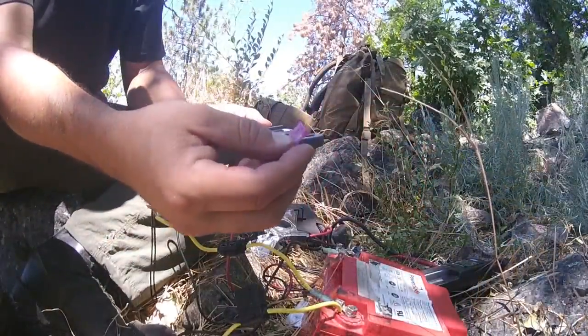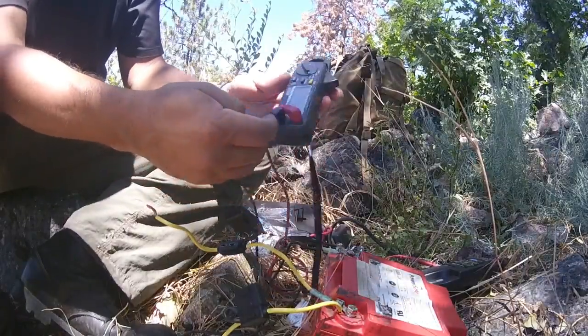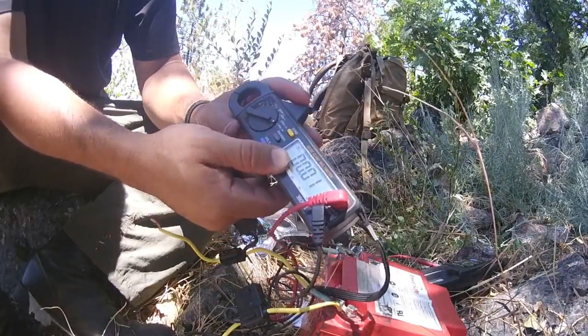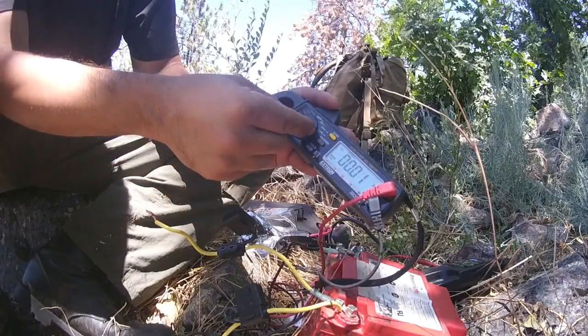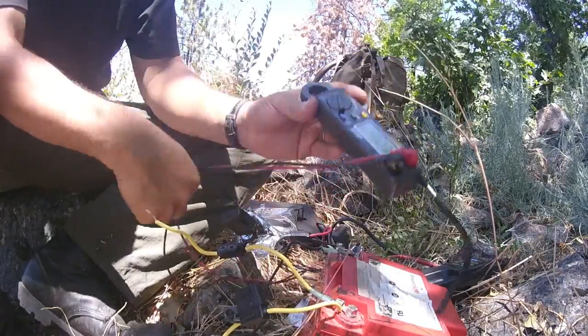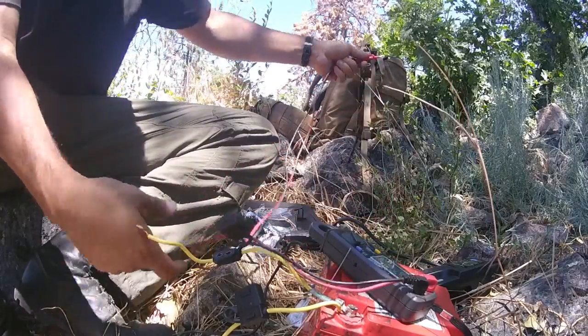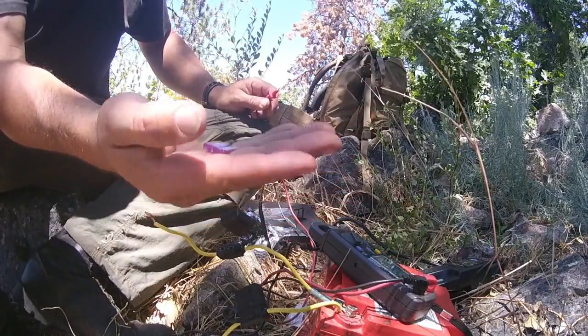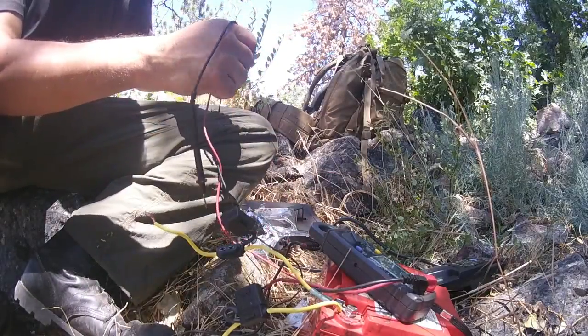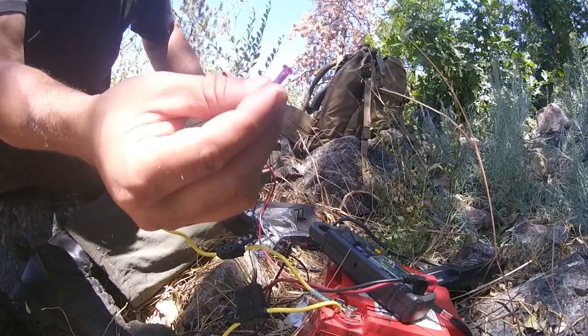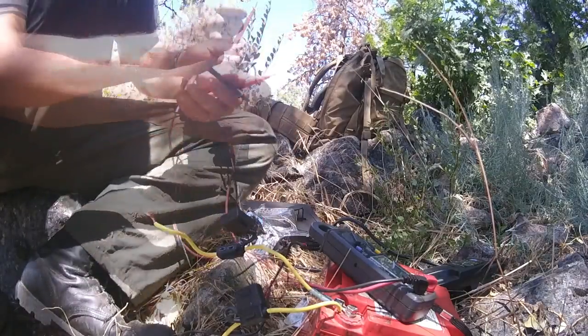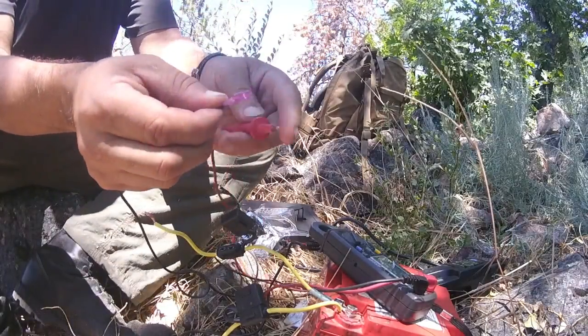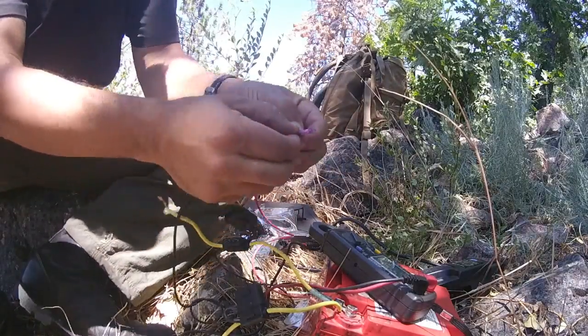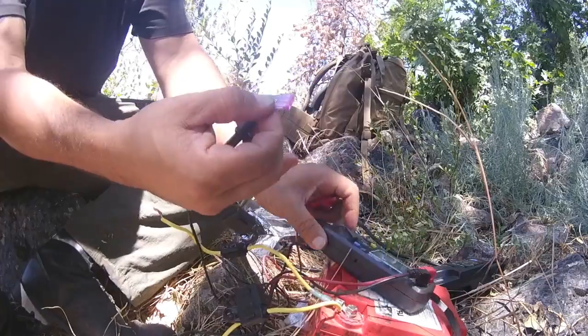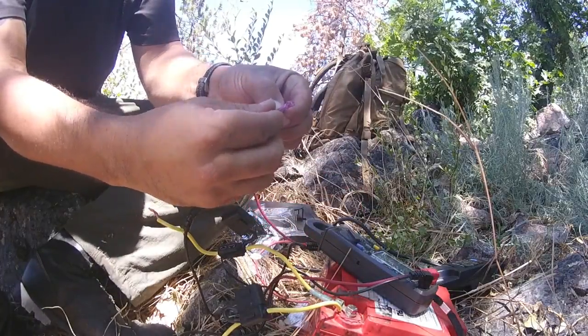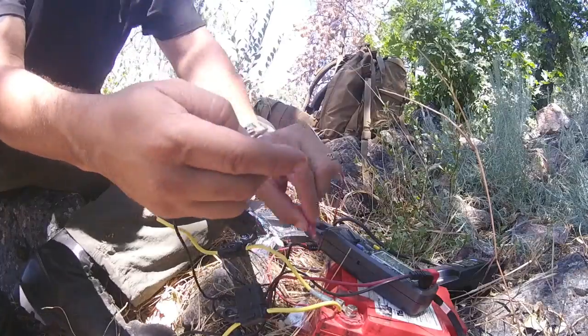So we took the offending fuse off, the suspected fuse. Now the high dollar multimeter here, we'll change it to ohms. In this particular model, it'll tell you how many ohms it is, and also give you a beep if it's a short, meaning there's no resistance. For a fuse, we want zero resistance, basically a piece of wire. So I go one end and then the other, nothing, no reading on the numbers here. It's maximum, an open circuit. No current is going to go through this device.